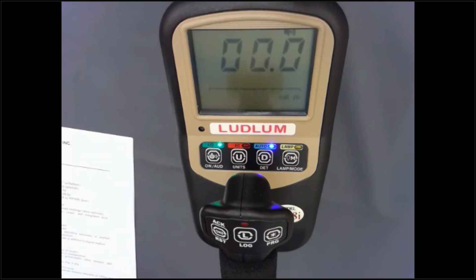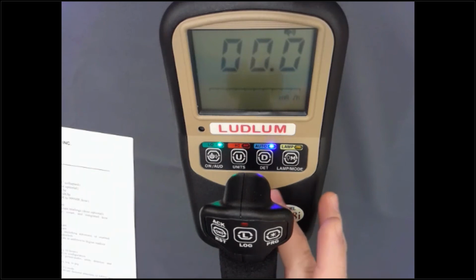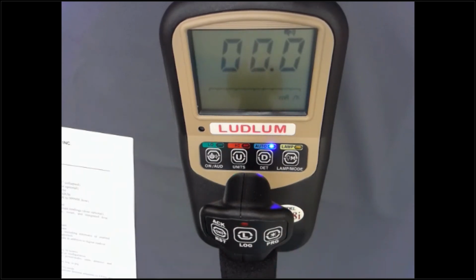To prevent oscillation that might occur, if you're taking a reading that's right at 2 R per hour or so, so that it's not switching back and forth between high and low detector, we actually put a minimum range on the high detector so that whenever it drops down to 800 mR per hour, it will then switch back over. So there's about a 1.2 R per hour kind of a hysteresis area in which the instrument will not switch.